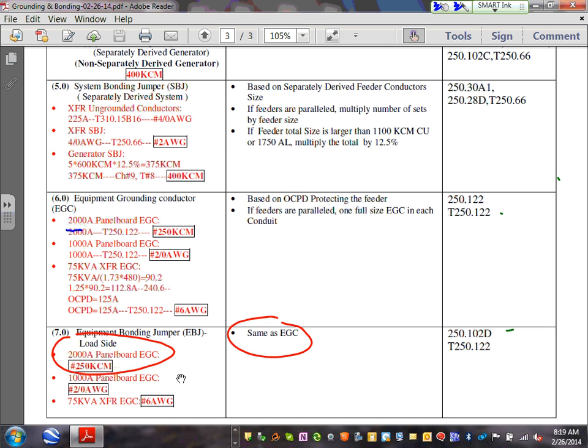Yes? Makes sense? No? Derek? Equipment bonding jumper, load side? Exactly. You size it as the equipment grounding conductor. What does it mean? When you bring these conduits here, here's the plan. You bring in the conduit from the top to the bottom. You have to bond the conduit to the box with a wire or with a lock nut or whatnot. That's called the equipment bonding jumper.